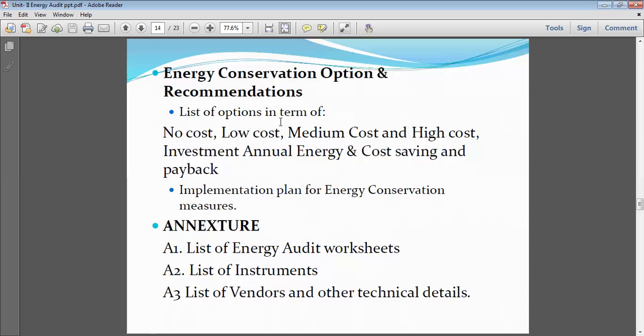Now some medium and high cost options: some motors are very old, having been rewound many times due to faults, and it is time to replace them with energy efficient machines. For example, in a process industry with 100 motors, 20 motors may be found suitable for replacement with energy efficient motors. When we replace with energy efficient induction motors, the efficiency increases, working power factor also increases, which increases the overall power factor and decreases maximum demand and kVAH.